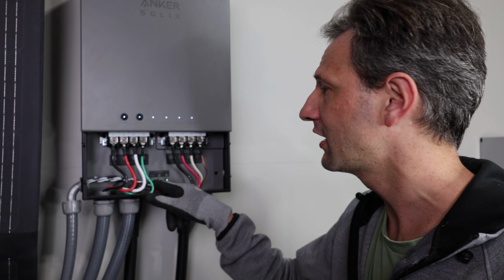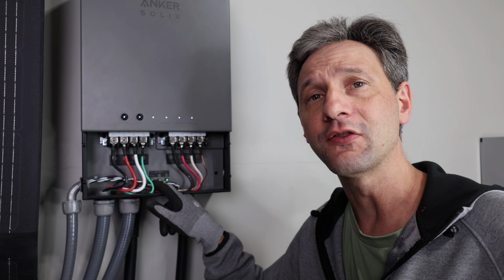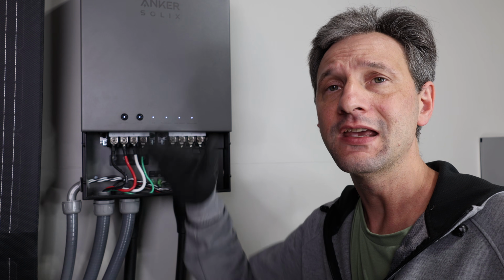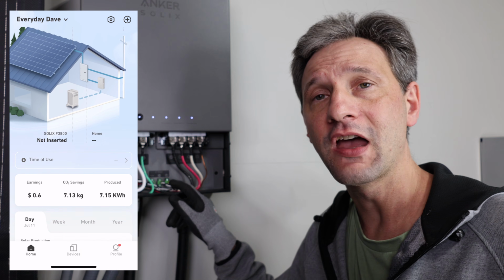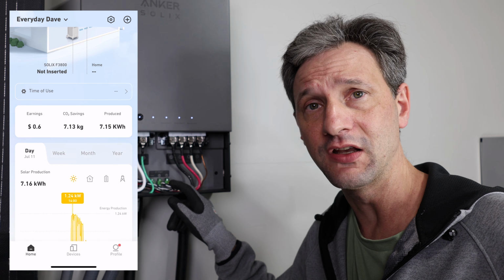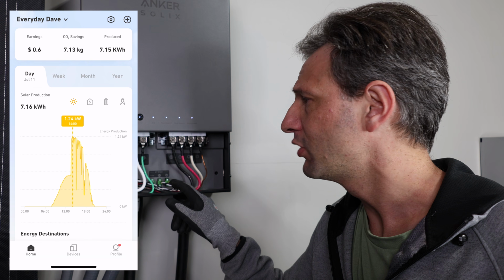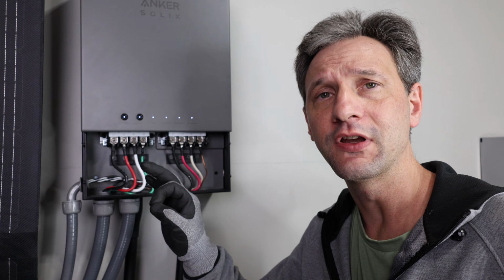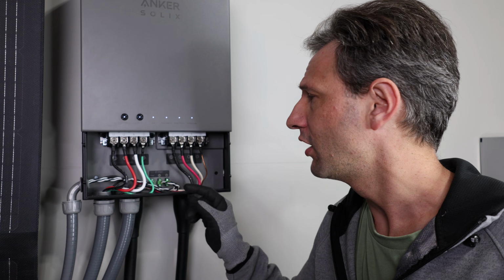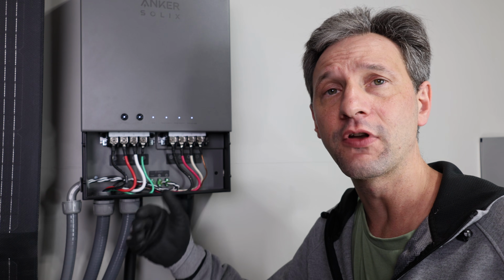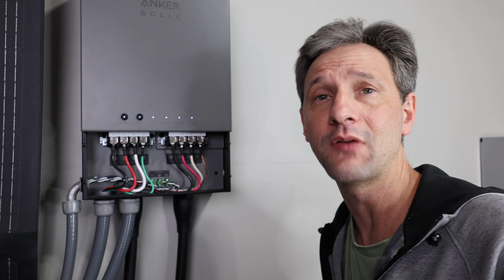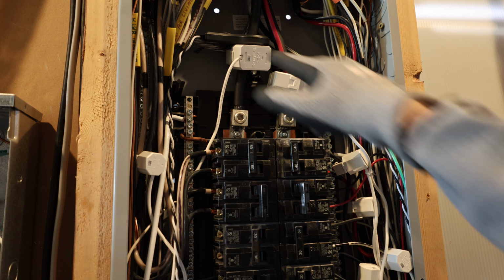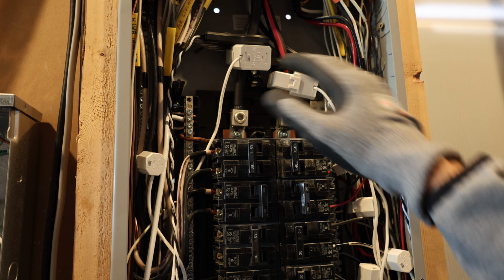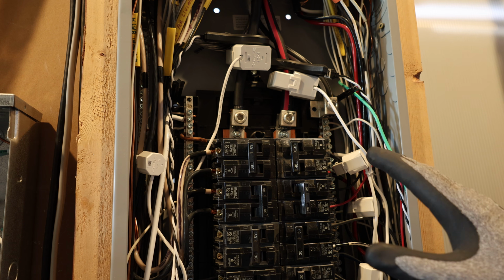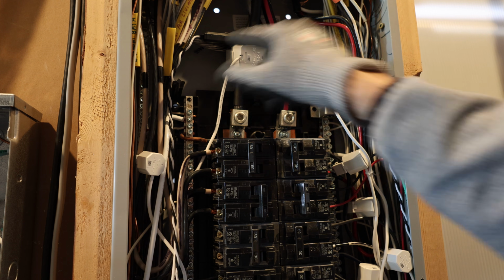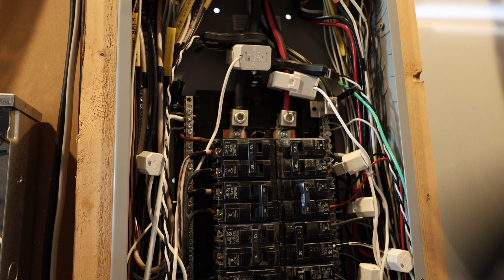Then there are a couple other connectors here - these are for sensors. They sense the amount of power coming in and out of your main panel. And if you have separate solar input, which in this case I do, I can put a CT sensor on that particular wire, and that allows me to understand how much solar is coming in and out of my main panel, independent of the solar coming in and out of these units directly. In my case, I already have sensors on my main panel for my Emporia Vue, so I can monitor everything with that system. I just clamped the sensors for the Anker Solix right above them, and that allows me to see if they match.